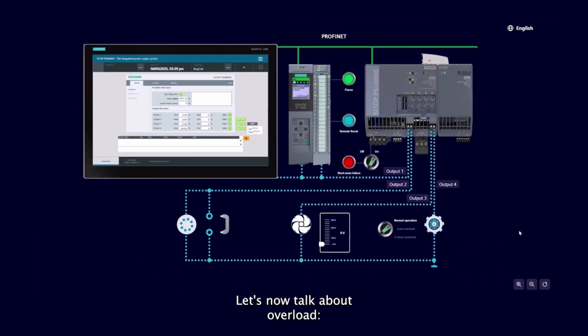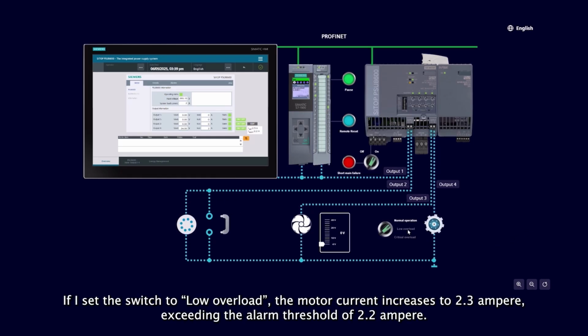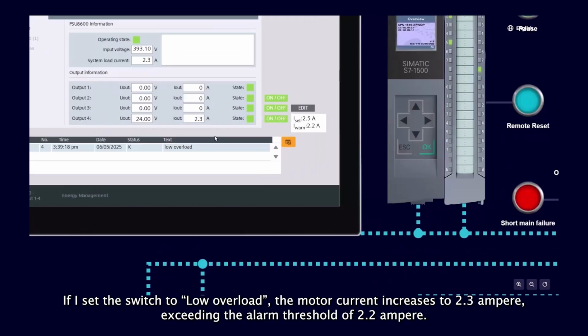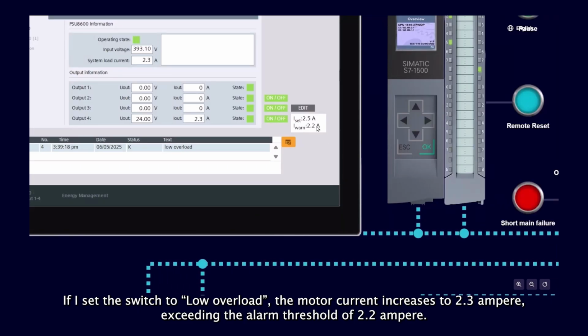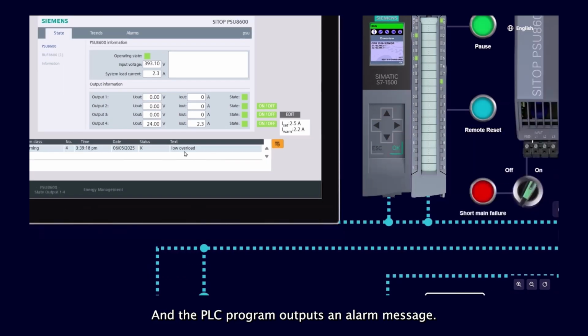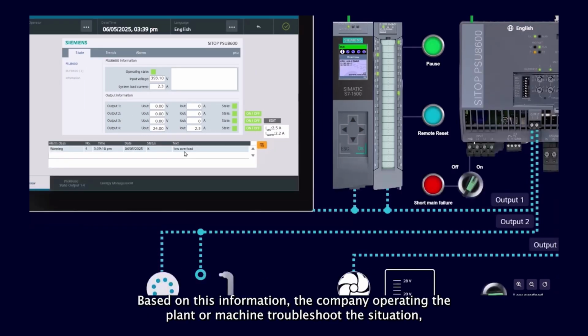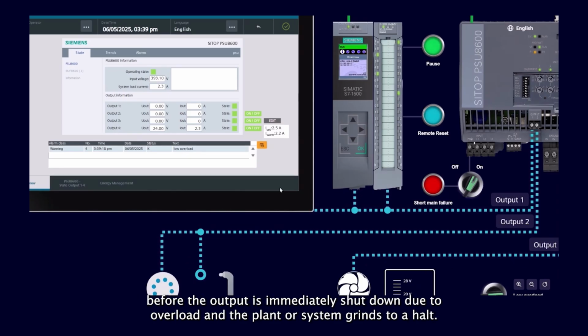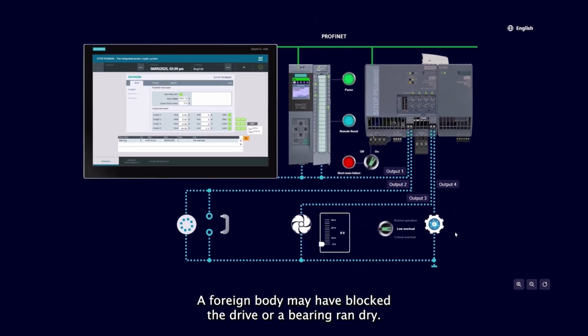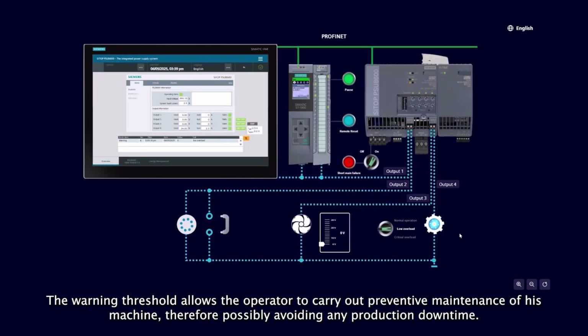Let's now talk about overload. If I set the switch to low overload, the motor current increases to 2.3 ampere, exceeding the alarm threshold of 2.2 ampere, and the PLC program outputs an alarm message. Based on this information, the company operating the plant or machine can troubleshoot the situation before the output is immediately shut down due to overload and the plant or system grinds to a halt. A foreign body may have blocked the drive or a bearing run dry. The warning threshold allows the operator to carry out preventive maintenance of his machine, therefore possibly avoiding any production downtime.